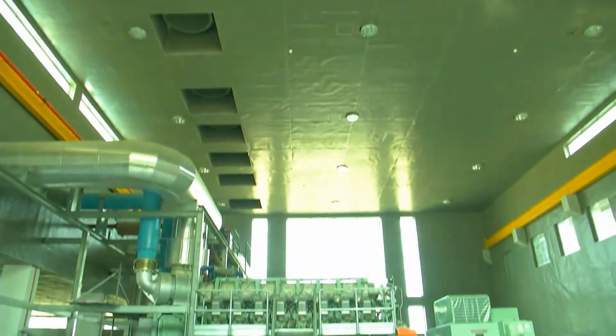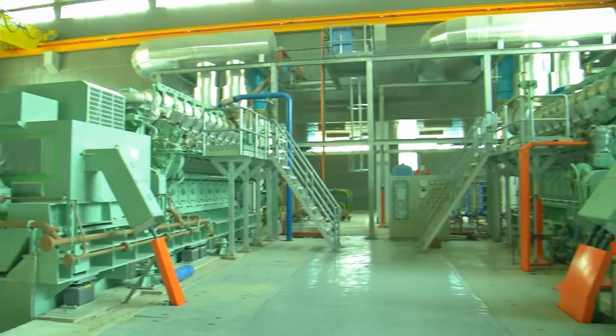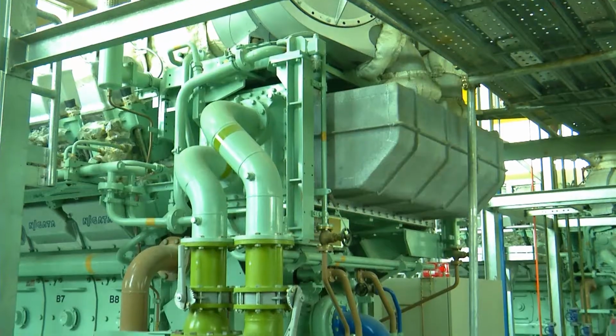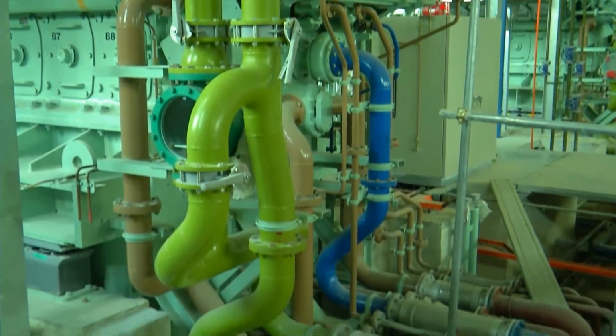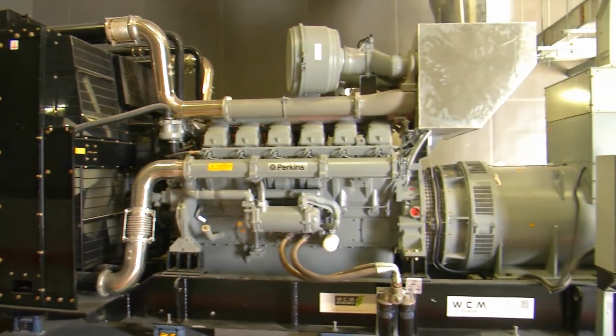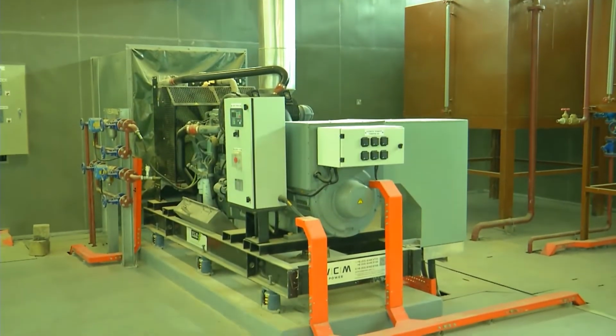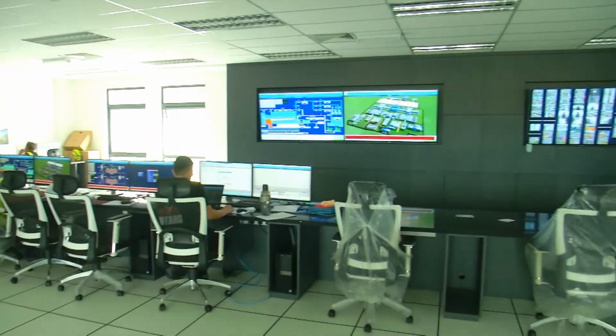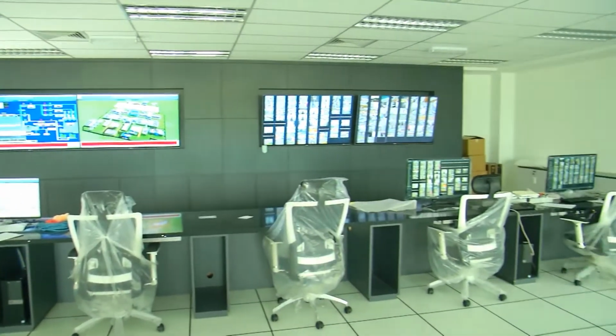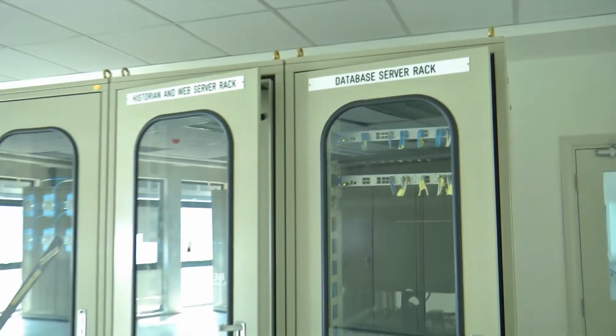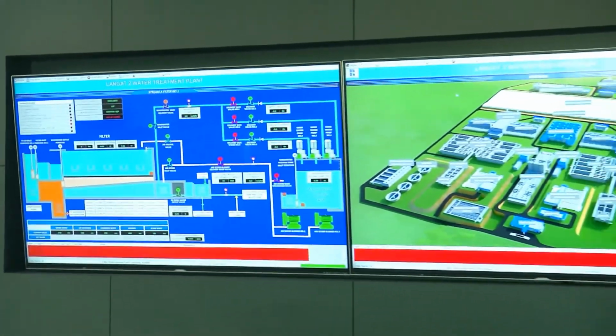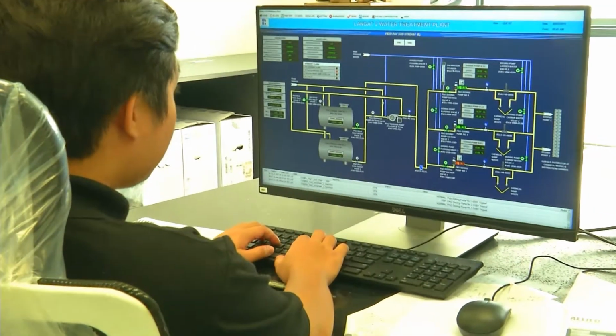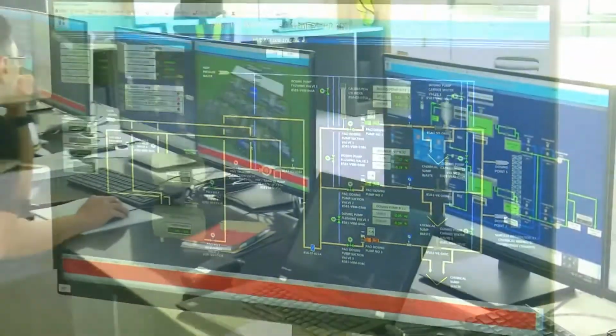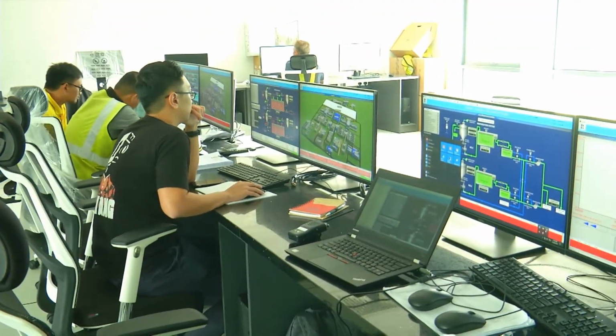The generators are sized to operate the treated water pumps during power outage. For the plant operation, separate standby diesel engine-driven generators are provided. Instrumentation and SCADA system. Instrumentation is installed throughout the treatment plant for the monitoring of the operation of the plant and water quality produced. The various plant data parameters shall be transmitted to the SCADA system, where the operator can monitor them at the command center.